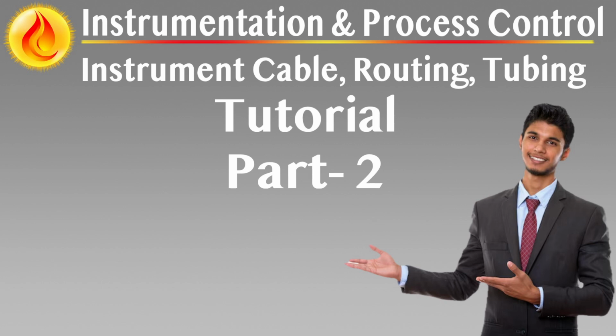Safety earth bonding for armoring and enclosures. All metallic armoring, SWA, braiding, SWB, and conductive sheathing must be bonded to the safety earth at both ends of the cable. Instrument housings, junction boxes, local panels, and cabinets must be bonded to adjacent trunking or structural steel through dedicated bolts and metallic contact interfaces.